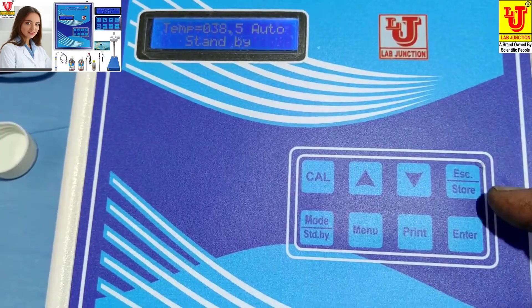Now it shows temperature and standby. Now, how to calibrate this? In this there is a cal key, up and down keys, escape and store key in one key, mode and standby key, menu for selecting parameters, print for printing results, enter for feeding. In this, mode and standby is to be pressed 2 times. Again this 2 times. Now I am calibrating pH.